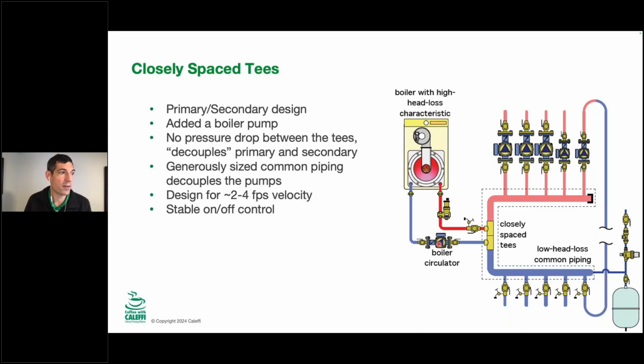Maybe it's a fixed speed, maybe it's a variable speed, but it's exactly what the boiler is asking for on the left side of the equation. And then these 5 pumps can come and go as they please as the zones open and close, and it doesn't affect the flow rate on the left side.